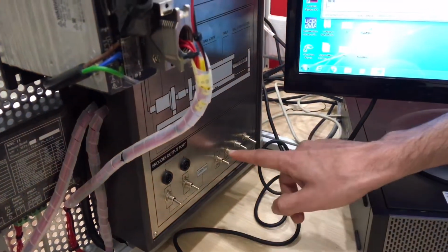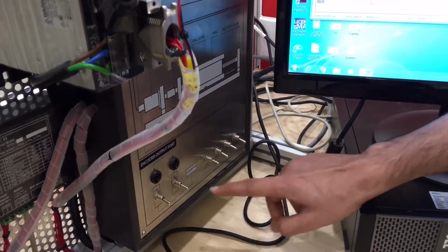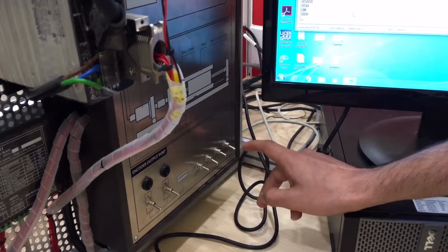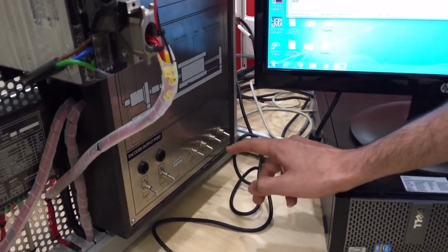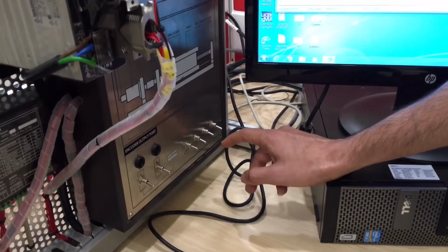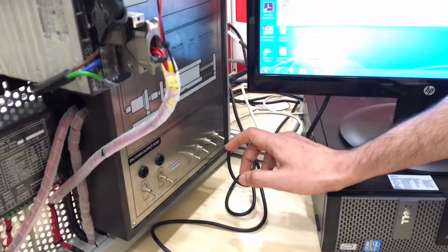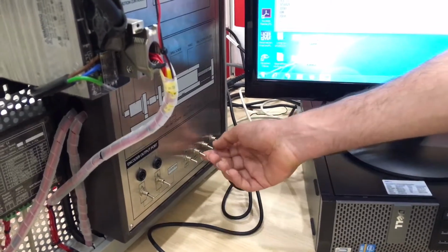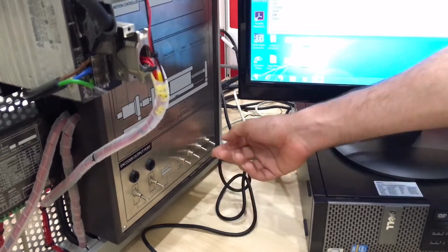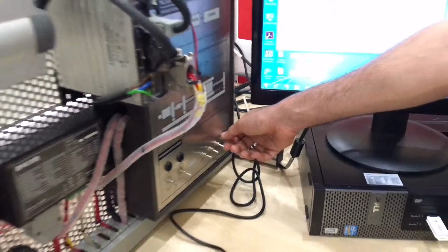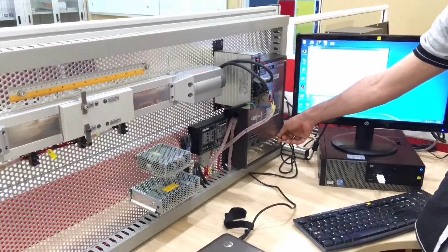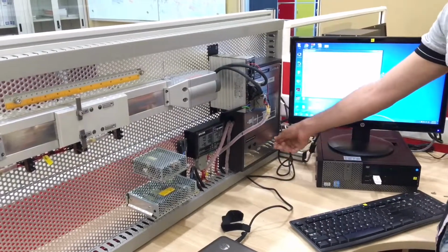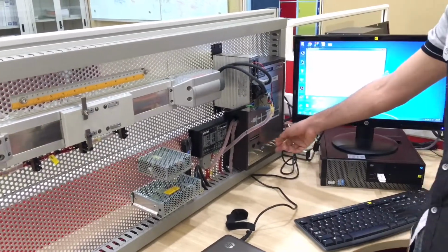Now, all of them being at the bottom means that all of them are 0. And this is a very good way to perform home without having to include the sensor. It's just uploaded into the machine just like that. So you key in all of them 0 and then you turn it on, it should actually move to the home button. We can't see that because it's already in the home position. So just turn it off and we move it to any value we already have inside.